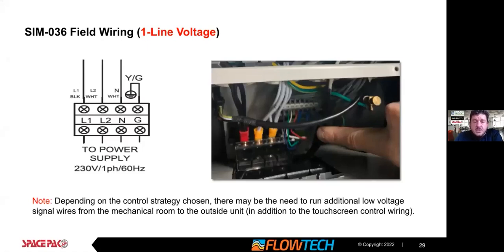The good news on these units is that they're very simple. They're complex when you look at them, you look at the control board, but for installation, it's really installing your 230 volt power. We need 4 wires on these units because they operate the circulator. So this is 4-wire 230 volt single phase.